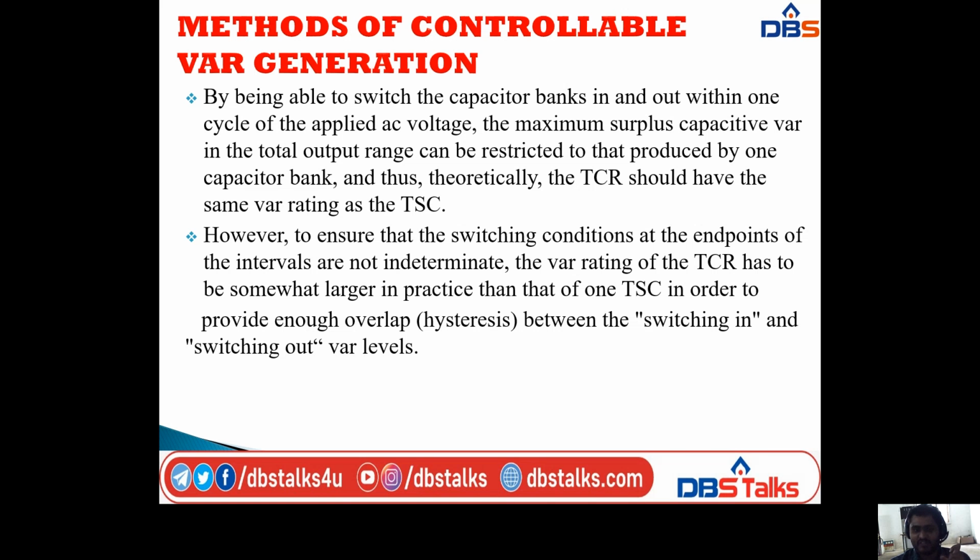Okay, so if we want to switch the capacitor banks in and out within one cycle of the applied AC voltage, we have to take the maximum surplus capacitor VAR, that means QC maximum, in the total output range restricted to that produced by one capacitor bank. Not considering all N branches, here we are considering only one. And thus theoretically the TCR, that means the thyristor controlled reactor, should have the same VAR rating as the TSC, that is the thyristor switched capacitor.